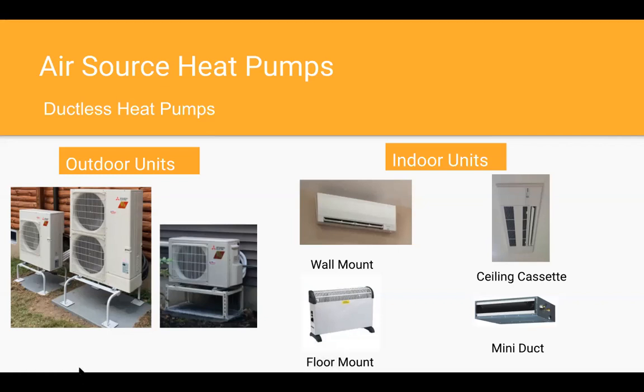The mini duct that you see there, that's nothing you would see. That's actually typically in an attic above a ceiling. It's called a ceiling concealed unit. And that can catch 4 or 5 rooms and save a lot of money by reducing the amount of zones that the system needs. It also helps from a design standpoint. When you have a lot of rooms with smaller loads, it helps you collect all those loads onto one zone, which is a much better way to design the system. You want to design around the load, not around the number of zones desired. So next slide.